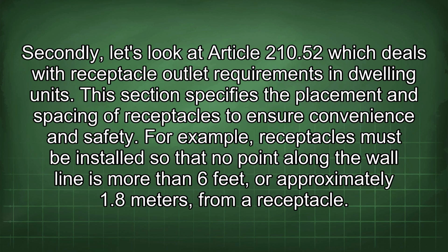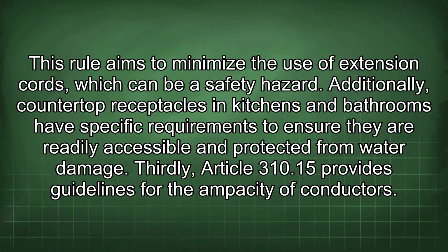Secondly, let's look at Article 210.52, which deals with receptacle outlet requirements in dwelling units. This section specifies the placement and spacing of receptacles to ensure convenience and safety. For example, receptacles must be installed so that no point along the wall line is more than 6 feet, or approximately 1.8 meters, from a receptacle. This rule aims to minimize the use of extension cords, which can be a safety hazard. Additionally, countertop receptacles in kitchens and bathrooms have specific requirements to ensure they are readily accessible and protected from water damage.